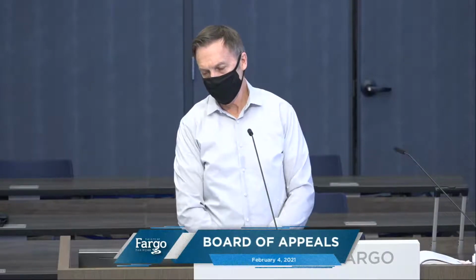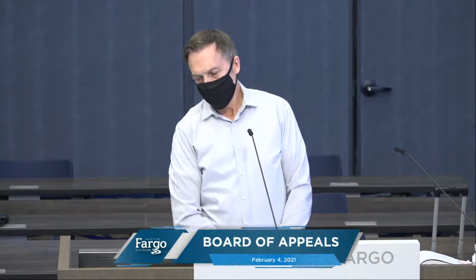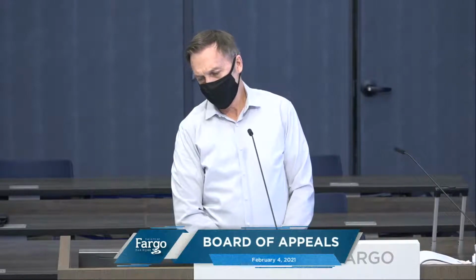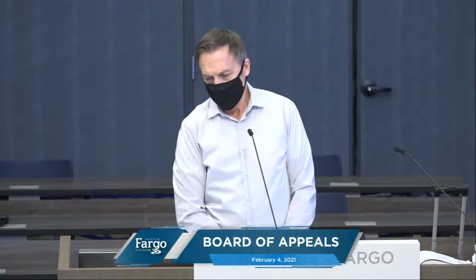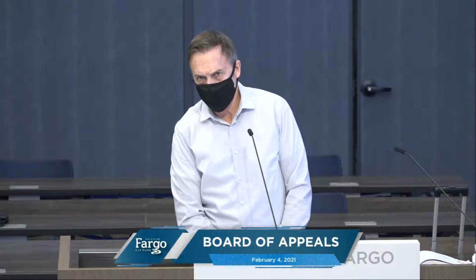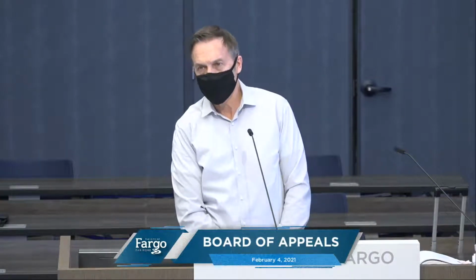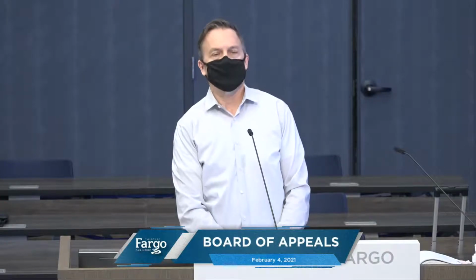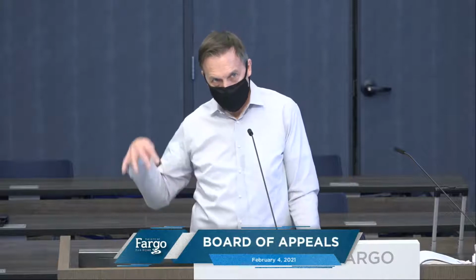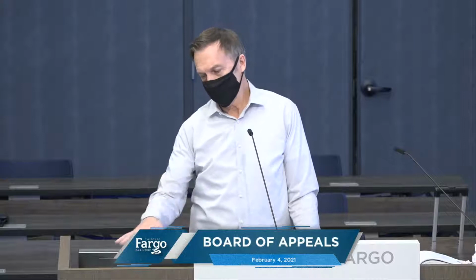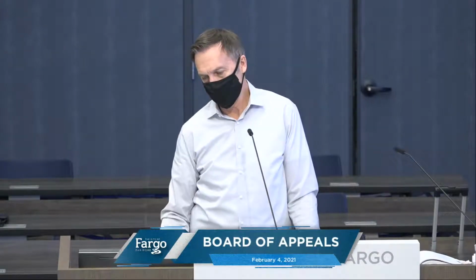A little bit on the continuity thing: Doug early on decided this was a room inside a building, because the way we look at buildings, anything with a roof is a building. Anything overhead is a building. Somebody builds a cantilever of 20 feet, even if it's grass underneath, we count that. They need the sprinkler below that area because there's a building up there. So as soon as there was a roof over it, we considered it in the building, and the continuity had to get up to that next deck.